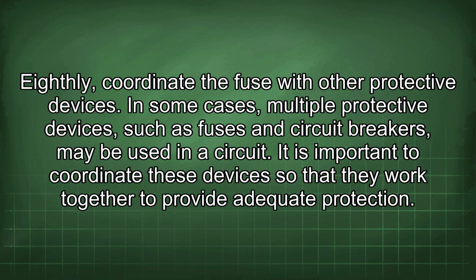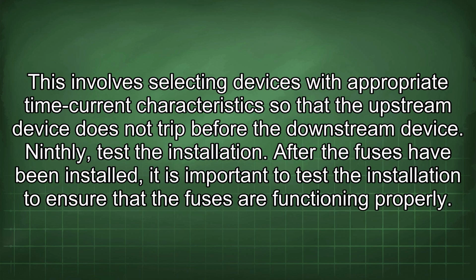Eighthly, coordinate the fuse with other protective devices. In some cases, multiple protective devices such as fuses and circuit breakers may be used in a circuit. It is important to coordinate these devices so that they work together to provide adequate protection. This involves selecting devices with appropriate time current characteristics so that the upstream device does not trip before the downstream device. Ninthly, test the installation.